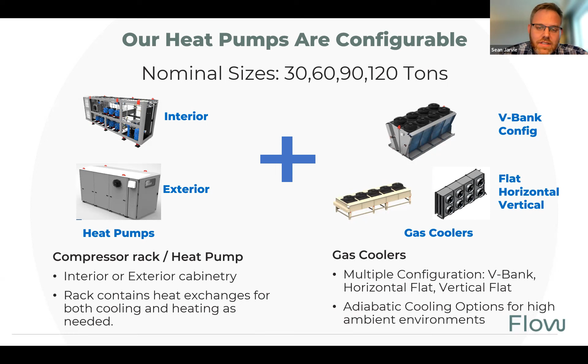Now we can set these up as either water to water or air to water heat pumps, and there are pros and cons to doing it both ways. Air to water, we can do a lot of that uneven load balancing, and they're really simple. These can be packaged all together on a single base rail and shipped as a unitized piece of equipment, which minimizes anything for a tech to do. They hook up water and power, and you're off to the races.